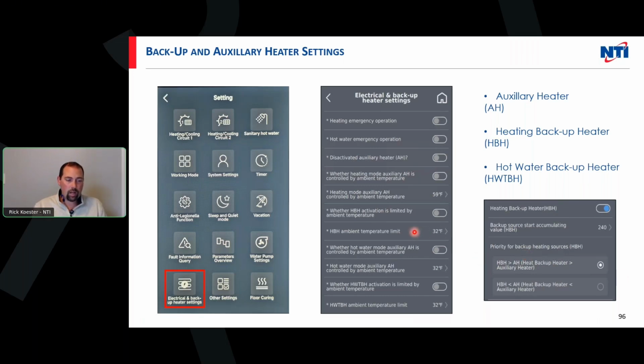We also have, as you see down here, ambient temperature. So basically any time that I'm less than 32 is kind of the limit. This is a limit for that, I'm sorry. And then this is going to be my, okay, at less than 59 degrees outside, I want to activate it. That's pretty high. I'll probably drop that a lot, but you can select what temperature you want to make that active. And the machine's going to look at its algorithm, see where its set points are, and it's going to control all of that internally of the machine.